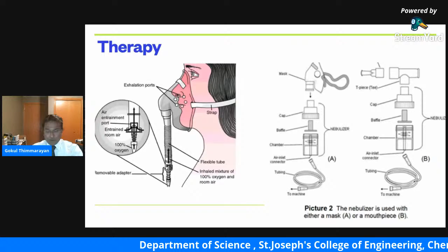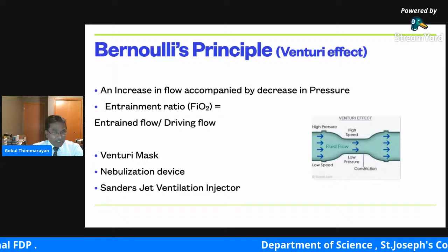So the principle involved is the Venturi effect, derived from Bernoulli's principle. As I mentioned, the entrainment ratio decides the percentage of oxygen that we want to give to the patient. Entrained flow by the driving flow is used in the same Venturi mask, the nebulization device, and also in jet ventilation during emergency situations, when we have to inject oxygen straight into the trachea through a cricothyrotomy or a tracheostomy. The jet ventilator also utilizes the same principle.